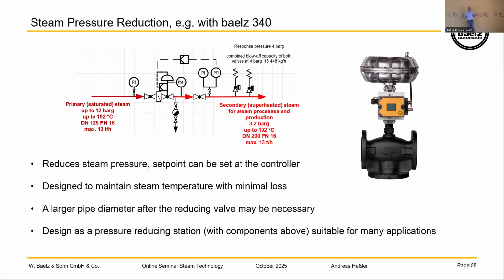To maintain the temperature with minimum loss, a larger pipe diameter after the valve is necessary. Why is it necessary? I explained it a lot of slides before: we have a much larger volume of the steam. So in this case, we're going in with a DN125, and we have to extend it after the valve to DN200 to have a good velocity of the steam.